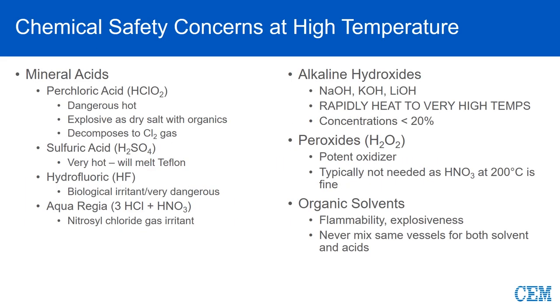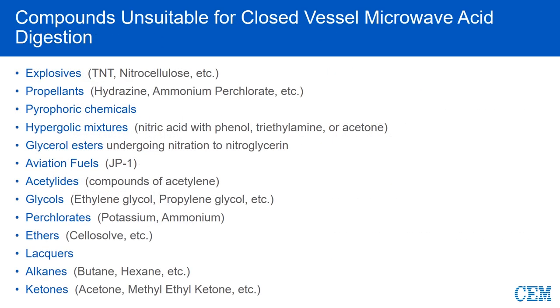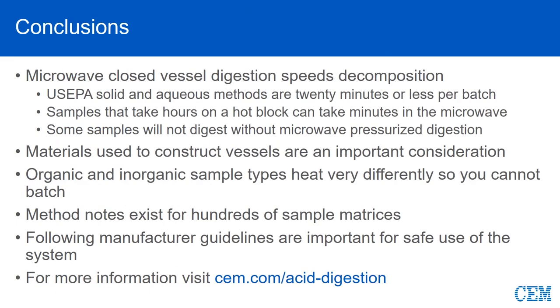Any time you are heating acids or solvents, whether by microwave or conventional heating, safety measures should be put in place to handle potential threats due to exposure of heat to such solutions. While microwave digestion provides a complete, rapid, and safe means of sample preparation for most samples, not all samples are suitable for digestion in a microwave. The compounds noted here can cause fires, explosions, or other catastrophic events and are not recommended for use with microwave digestion equipment.